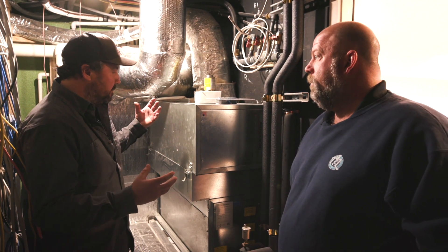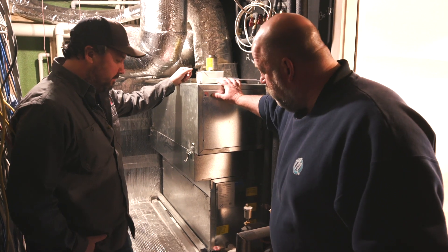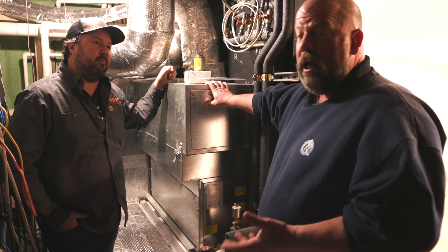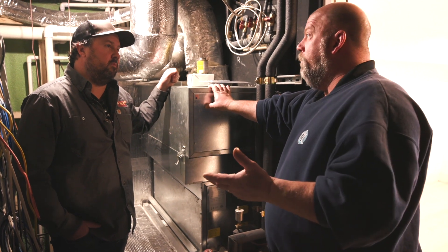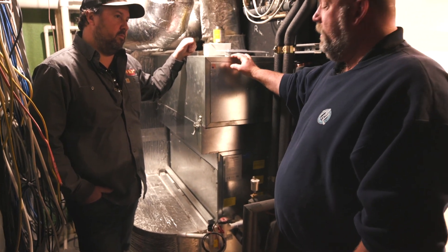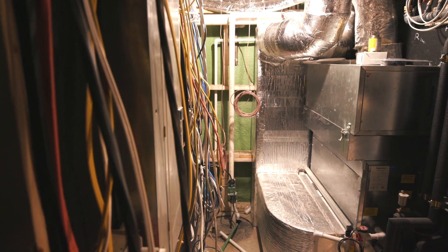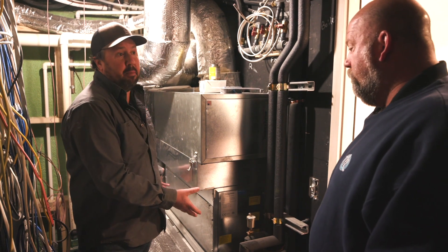So how does this unit work? The Unico is a modular unit — you can pick and choose cooling only, heating only, or both. This job calls for heating and cooling, so we have our heating section, our cooling section, and our fan section. Return duct comes in here. As you can see, this room is a little tight — we had to get creative. Our discharge goes out, and we have 21 outlets on this. This is a three-ton unit.